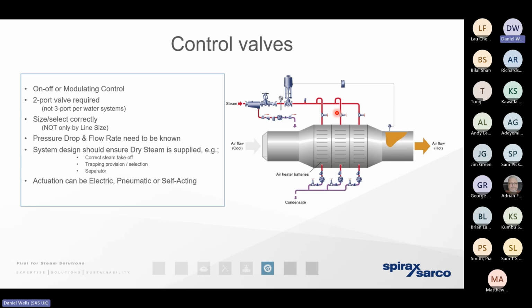Speed of sound, 350 miles an hour, 440 miles an hour. So any moisture, any rust, any scale, it's going to rip the guts out of that control valve and cause it to erode and fail very, very quickly. That means we've either got a high energy inefficiency due to the steam weeping away, or we've got a very poor control of temperature of the process. So as a rule of thumb, a control valve, when it's correctly sized, should be approximately 2 pipe diameters smaller than the upstream connecting steam pipe.